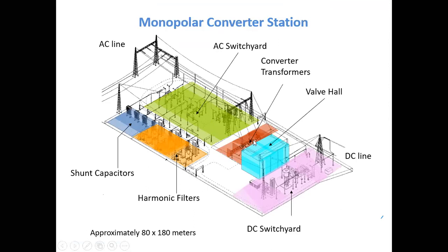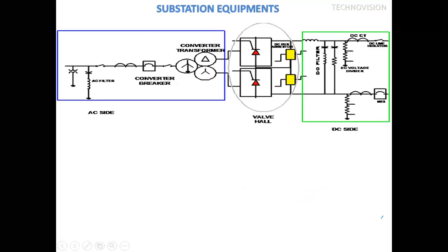Then there are the converter transformers here, and after the converter transformers there are the thyristor valves. These are the indoor valves which are suspended structures. These are hanging from the ceiling. And here we have a DC switchyard where DC filters are there, and this is the DC line. This is, we can say, the first tower. If it is a rectifier station, it is the first tower present in the DC switchyard. From there, there is a connection with the DC line. So this is the structure of the converter station.